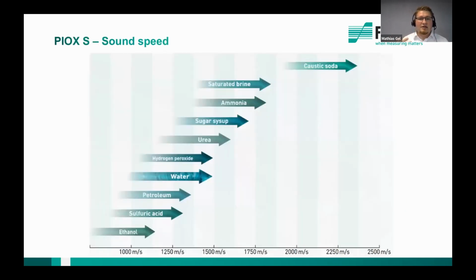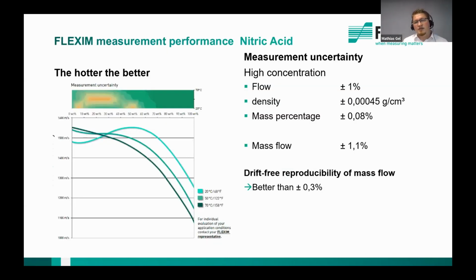And then the sound speed is, to give you a very rough idea here, where typically certain substances have the sound speed. So caustic soda is up here at 2,000, 2,500 or even more meters per second, right? That's how we measure the sound speed. Water would be normally at 20 degrees Celsius around 1,500 meters per second. And then if we look at acids like sulfuric acid, nitric acid, and so on, all of this is then below water. And so as we can maybe see quickly here at the example of the nitric acid, we have here the sound speed, we have here the concentration, and we can see that with the changing concentration, the sound speed changes.